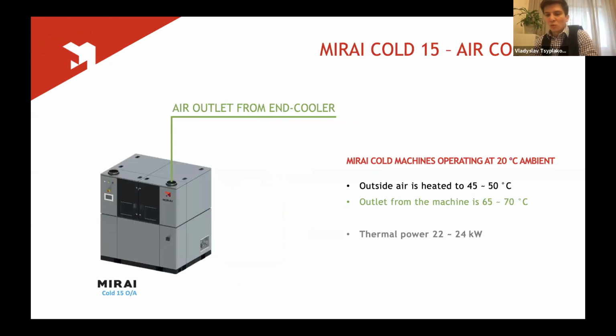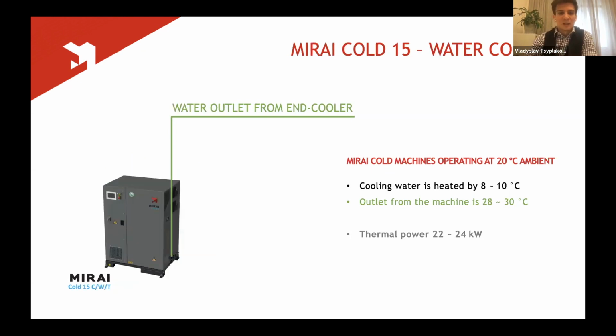Coming down to the air-cooled machine, if the air temperature outside is +20, we can heat this air up to 70 degrees with the thermal power of 22 to 24 kilowatts. And we have actually realized a project like this, and I'm going to talk about it a little bit later. So with the following machines, this is our new product that we announced this year. It's still in the body of the smallest machine, but we can harvest thermal power, which otherwise would be just thrown into the water circuit, of up to 24 kilowatts, but low potential.